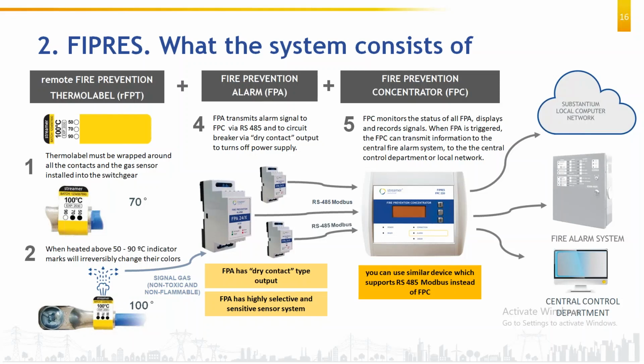Okay. Now, whenever you install this particular sticker on the terminal block, the first thing that will happen is it will adapt to the temperature of this particular lug. Whenever you wrap it in normal condition, all three pre-indication dots are white. As soon as you wrap it, if the temperature of the terminal block is 70 degrees Celsius, for example, the 50 and 70 dots will turn black. And it will remain like this as long as the temperature of the terminal block remains 70 degrees.